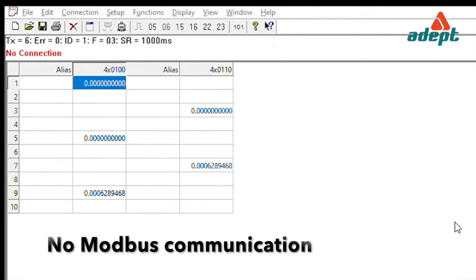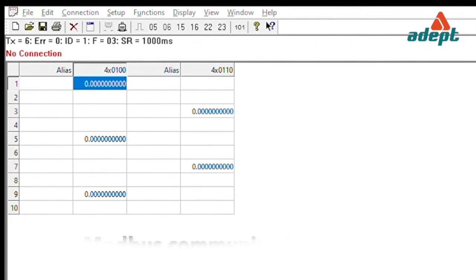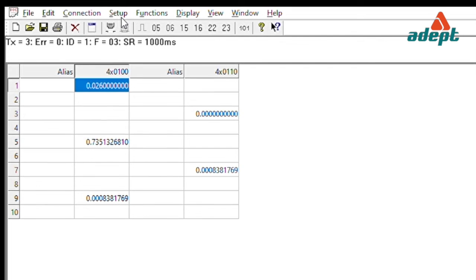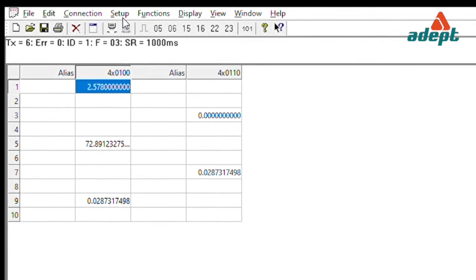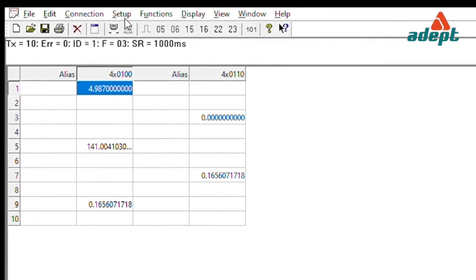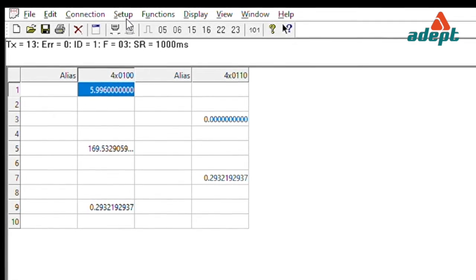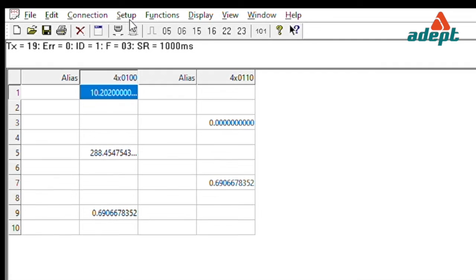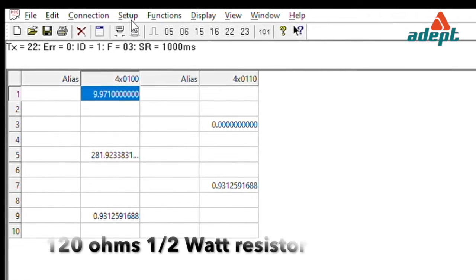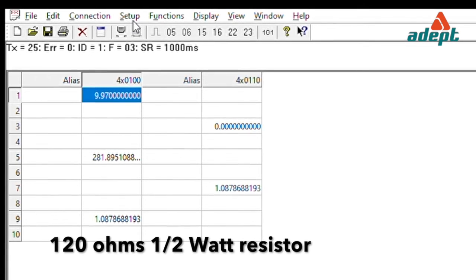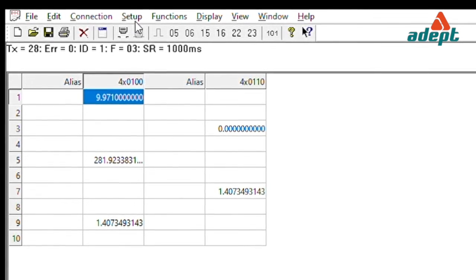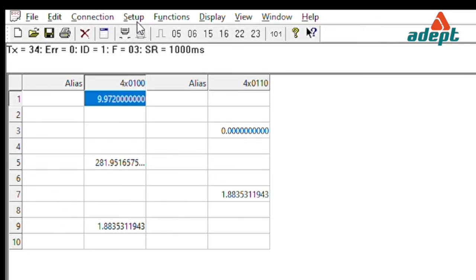If there is no Modbus communication, first confirm that the Modbus master device is connected to the correct terminals, all slaves are connected to the master in a single linear multi-dropped configuration, there are no nodes within multiple branches of multi-dropped slaves, the slave farthest from the master has been terminated with a 120-ohm half-watt resistor, and all slaves have been assigned only unique slave addresses. The master is correctly programmed with addresses to access only the intended slaves.